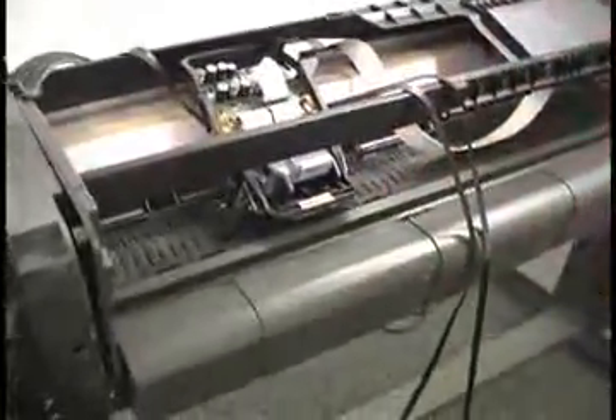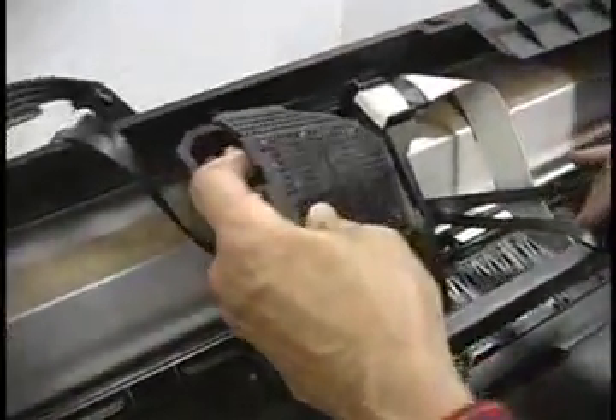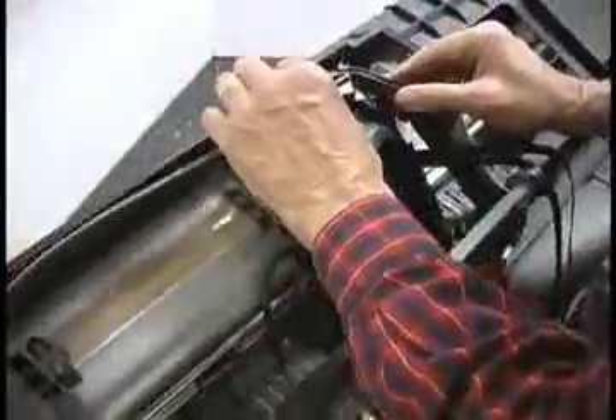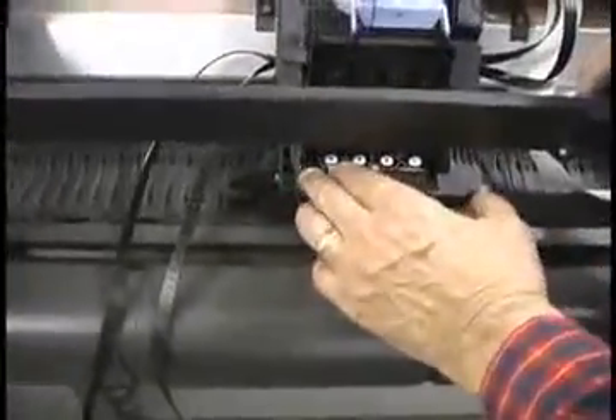Okay, let's put the carriage top back on. There's a tab right here that fits through a slot, tab A and slot B, as it were, just like that, and it clicks in. Now I can put the tube system back on, and that just fits into place. What you want to do is get this slot right here over this edge. This slot, this edge. And when you push down, this thing's going to click into place. Now all we have to do is tighten the screw that we took loose a little earlier. And that was the T8.